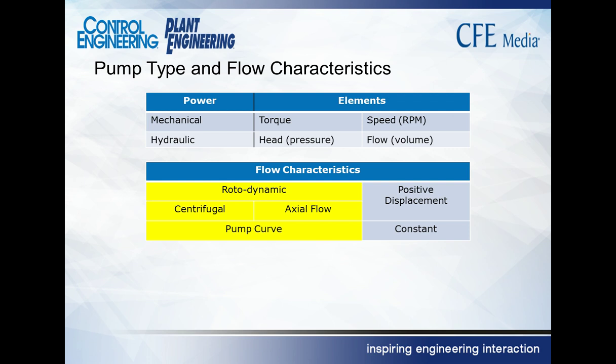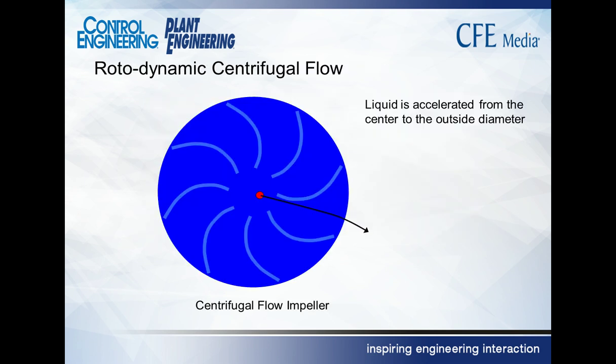There may be some opportunities for energy savings with positive displacement pumps and variable speed applications, but those are not part of the subject today. So we're going to focus in on rotodynamic pumps, both centrifugal and axial. A centrifugal pump is one where the liquid is accelerated from the center of the impeller towards the outside. So the flow is from the middle outward on a centrifugal pump.